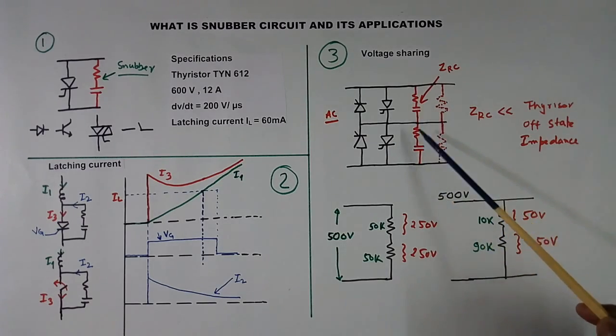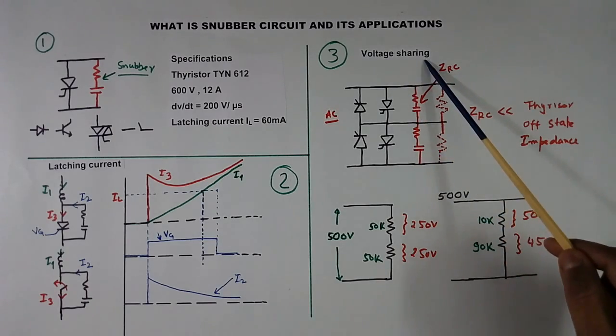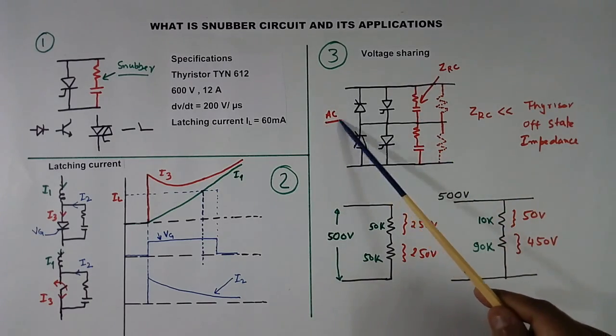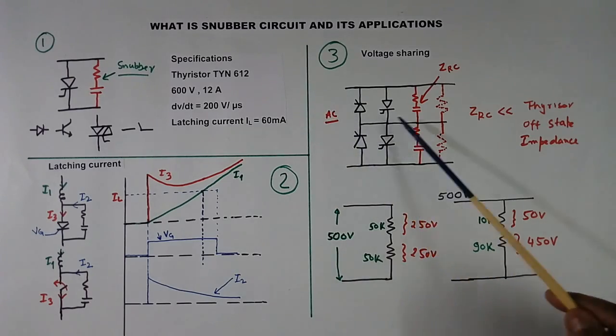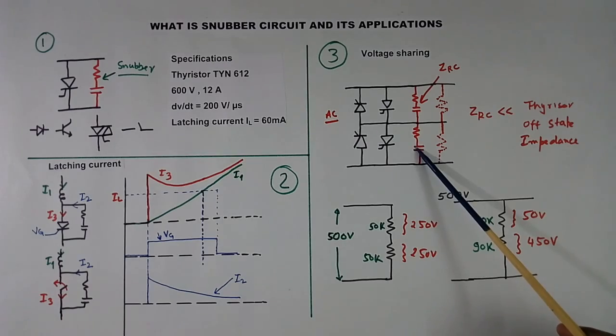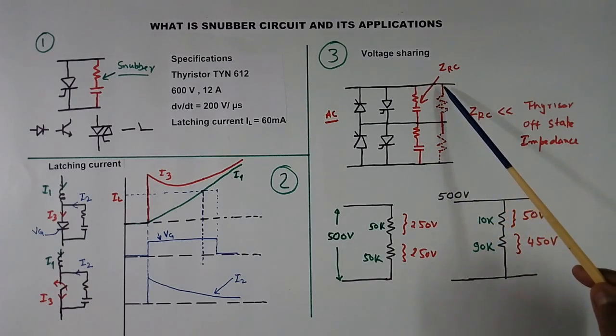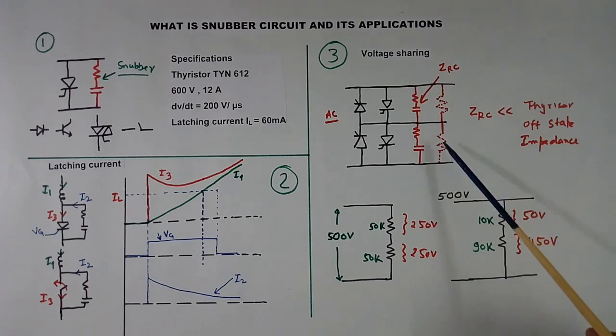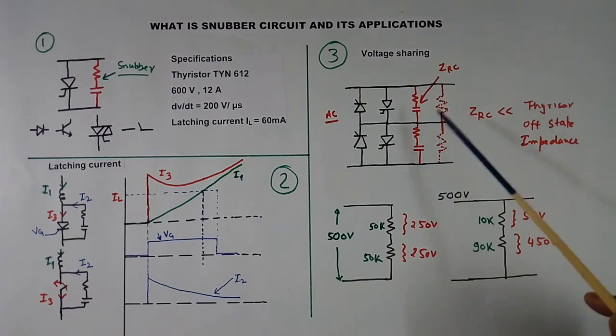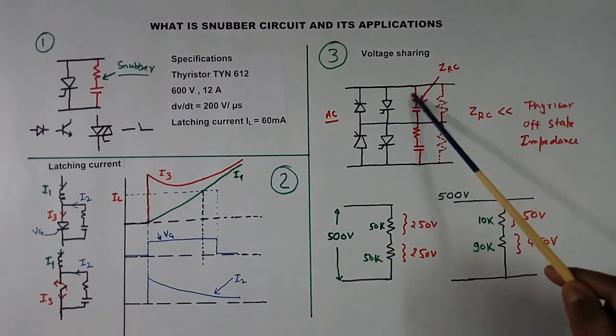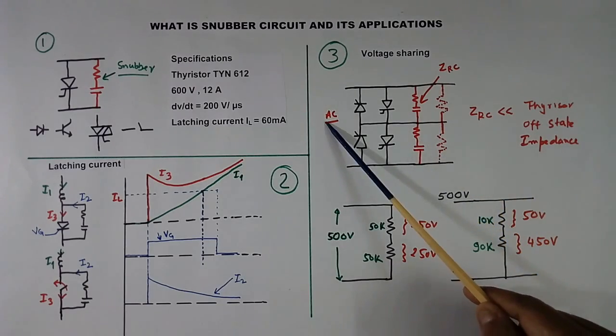But this snubber circuit will help in voltage sharing if you give AC voltage. If you give DC voltage, it does not help in improving voltage sharing. In that case, one resistor is connected in parallel of this. This is not snubber circuit. We connect one resistor here and here. This decides the voltage sharing. This helps only during DC input.